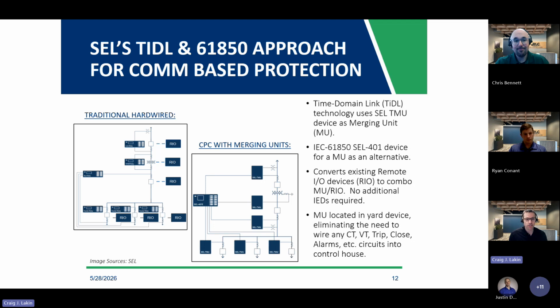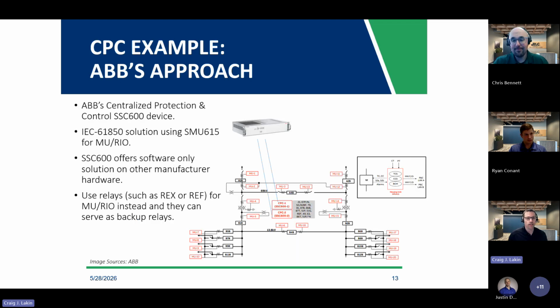So moving on to the next example we have is ABB's approach to this. So ABB also offers kind of the first tried and true, industry stamped centralized protection device called their SSC 600 device. It is a full-blown centralized protection computing platform. So it's rack mounted. It's not just leveraging existing relaying technology. It's a standalone new unit. They have their own merging units available, or you can obviously subscribe to any other publishing IEC 61850 merging units by other vendors.